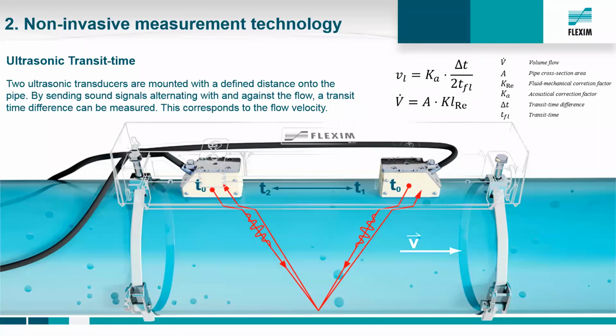The time the ultrasonic signal travels from one transducer through the pipe is called transit time. The ultrasonic signals are sent alternating in and against the flow direction. The signals with the flow direction of the media are faster than the signals against the flow, like a swimmer who is swimming with or against the current. The difference of the transit times is proportional to the flow velocity of the fluid. Considering as well the cross-section of the pipe, the volume flow can be calculated.